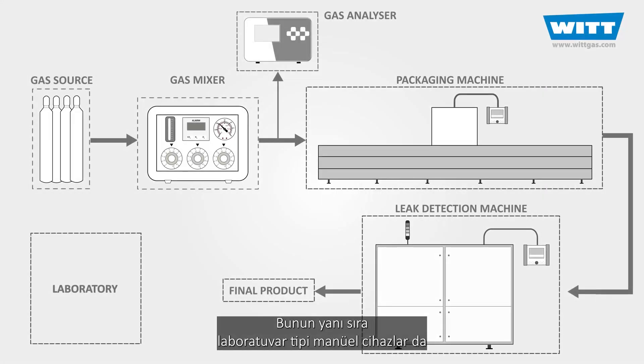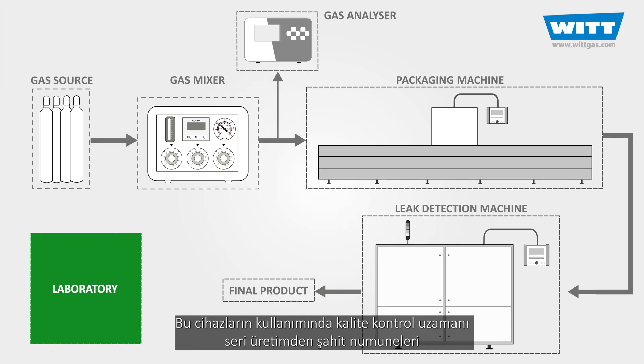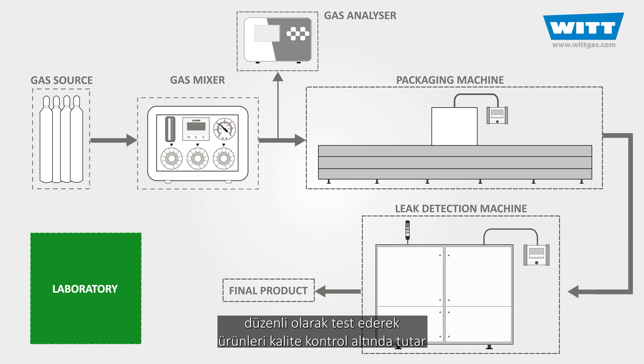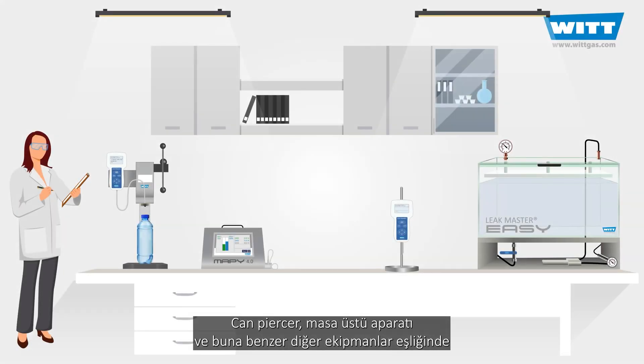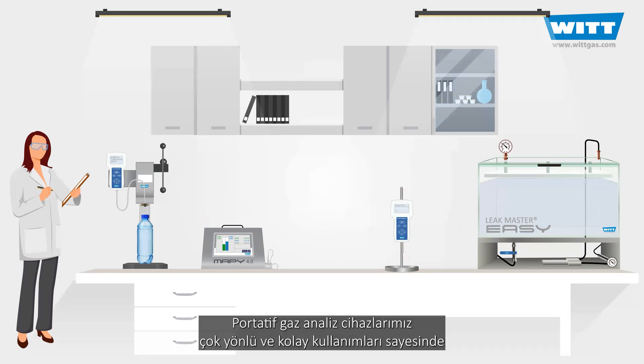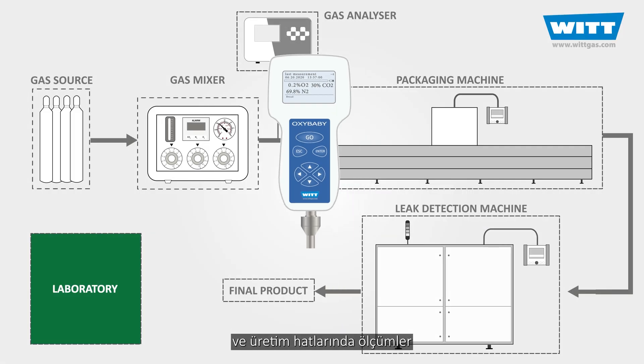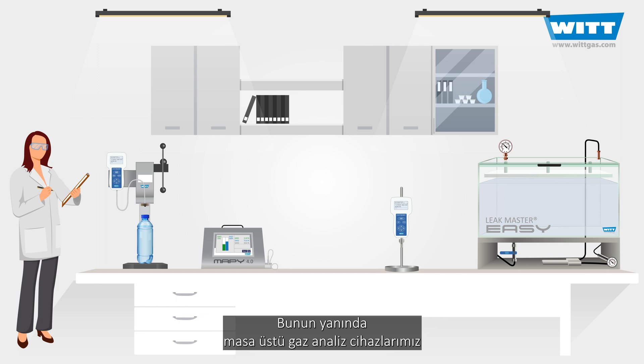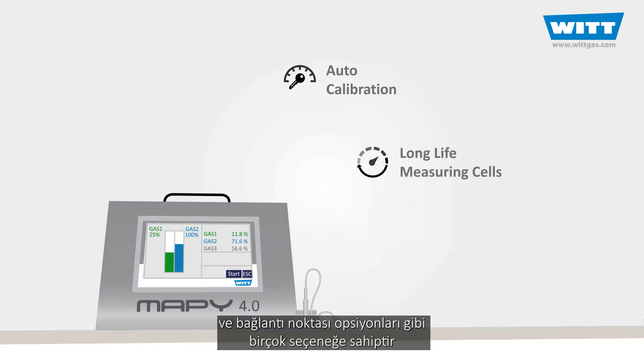In addition to the mentioned equipment in the production line, laboratory testing devices are used as well. Quality control experts perform tests on randomly chosen packages to check the quality and suitability for sale. Along with accessories like can piercers, tabletop or portable gas analyzers can be used for analyzing gas concentration inside different kinds of packages. Portable analyzers are highly versatile and easy to use, suitable for laboratory or production line use. Tabletop analyzers can have additional options like auto calibration, long-life measuring cells, and more communication ports.